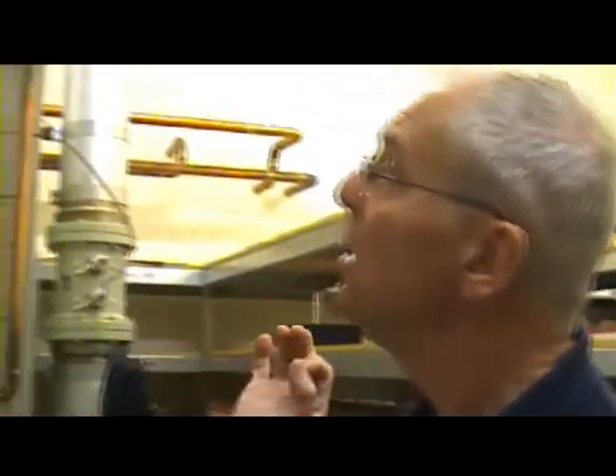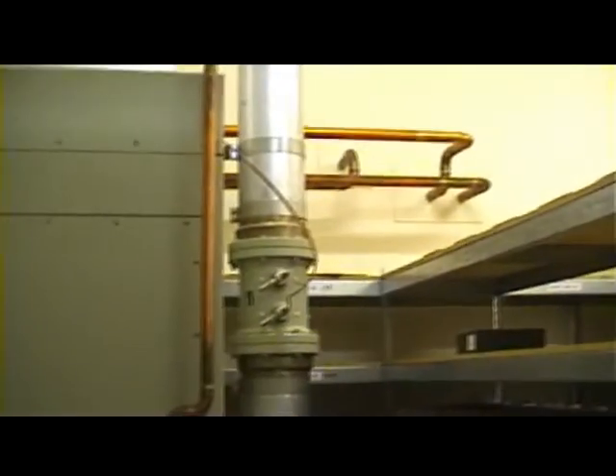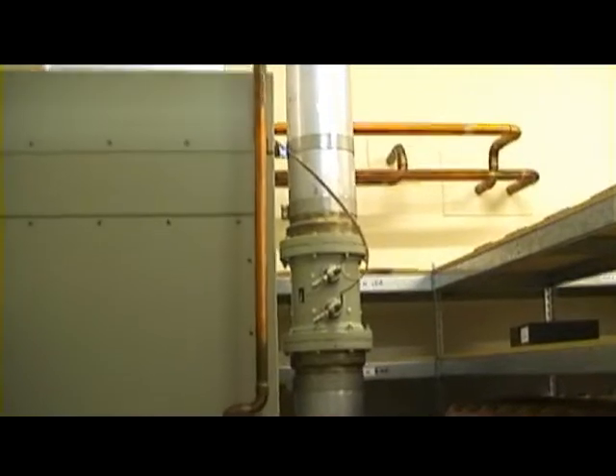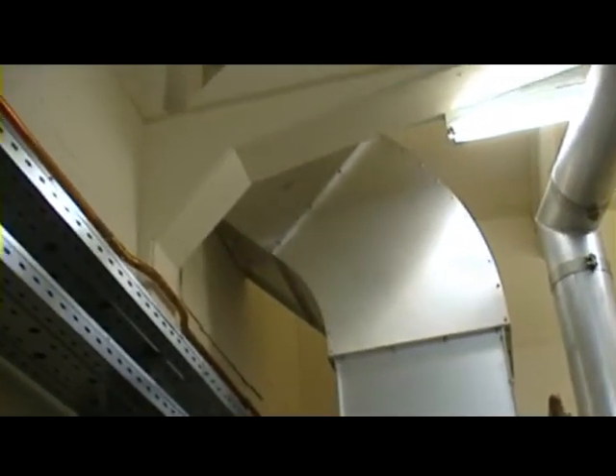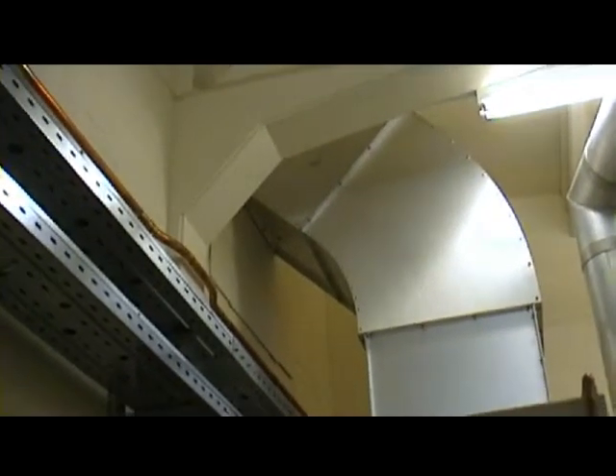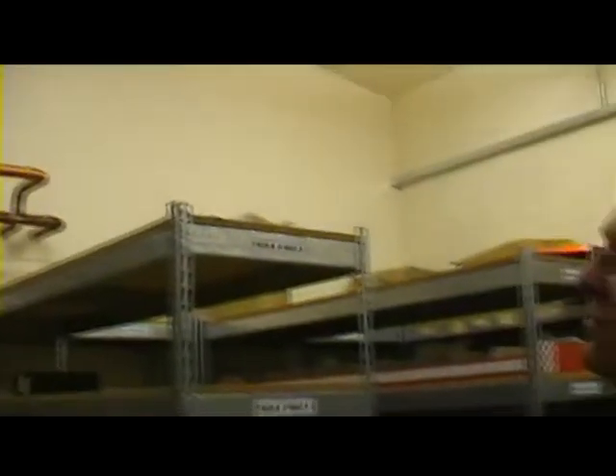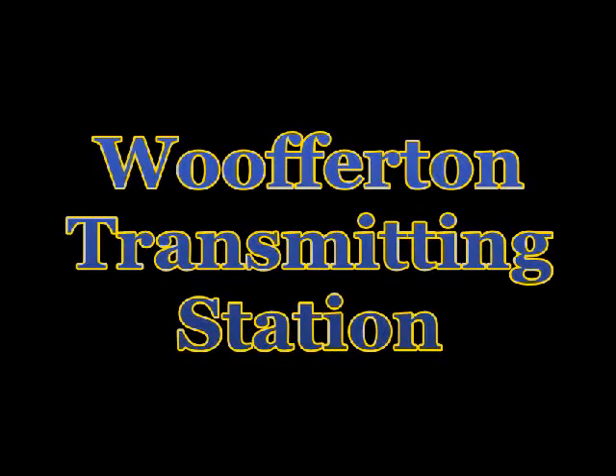That goes around the corner and goes horizontal above the transmitter to the outside world in the screened enclosure. But as it goes along, both the diameter of the copper and the spacing gradually taper narrower and narrower and further and further apart. And eventually it gets to 300 ohms. And that then matches the existing system here at Woofferton. So that's the extra bolt-on bit from RIS. So you can use modern 50 ohm transmitters into old-fashioned 300 ohm antennas. There it is.